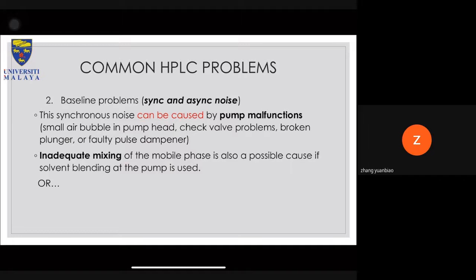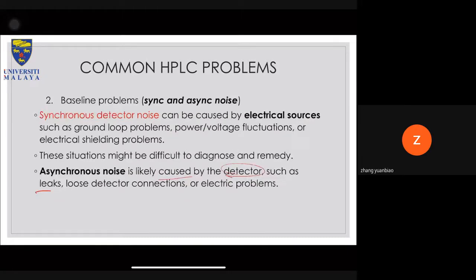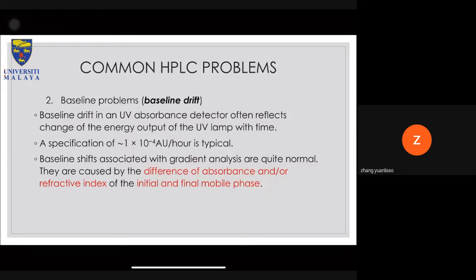Asynchronous noise, on the other hand, is likely caused by the detector, such as leaks, loose detector connections, or it can also be an electrical problem. All right. Baseline drift. Baseline drift in UV absorption. Okay, this is a picture after this.